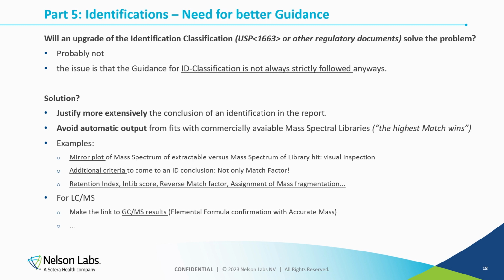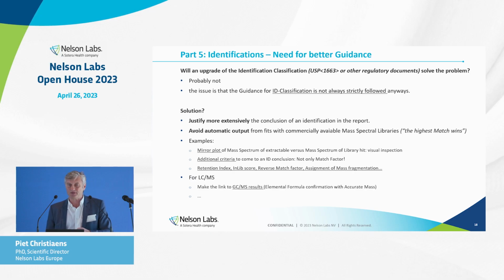What I think should be done is that you need to justify how you have come to a conclusion on the identity of a compound in a report. You have to show the mass spectra, maybe a mirror image with the database or with a library, the NIST library, for instance, to show that it's good. You also can use other criteria that are in NIST and Wiley. For instance, Ward talked about the retention index, which avoids reporting crap already for a large part, or reverse match factors, or fragmentation assignment, and so on.